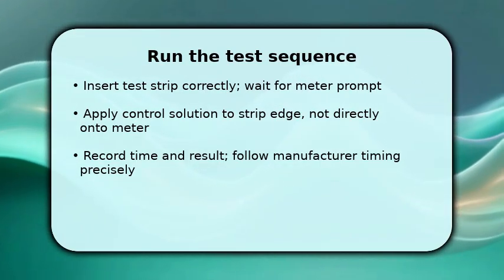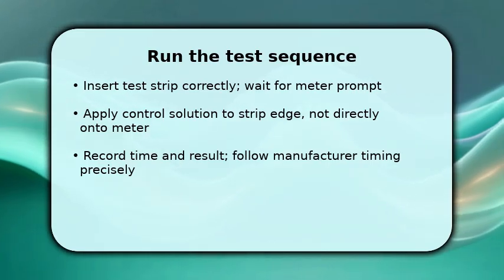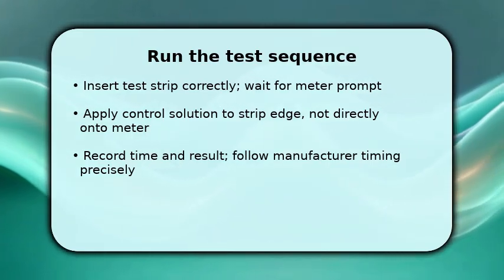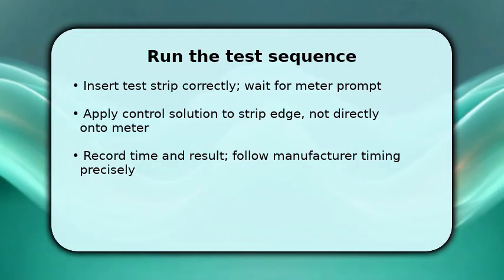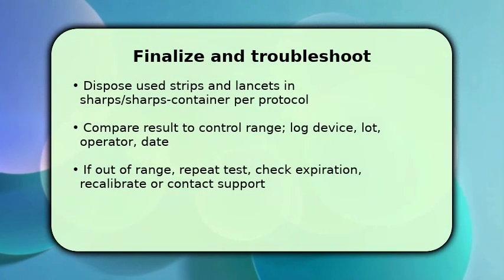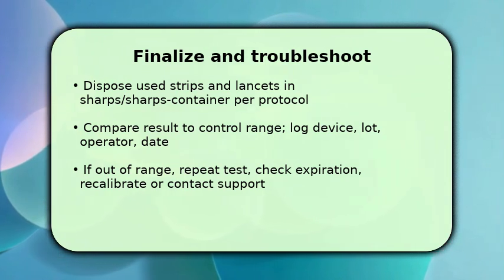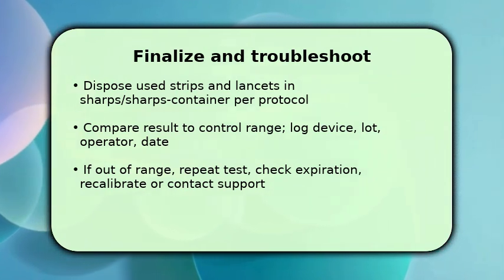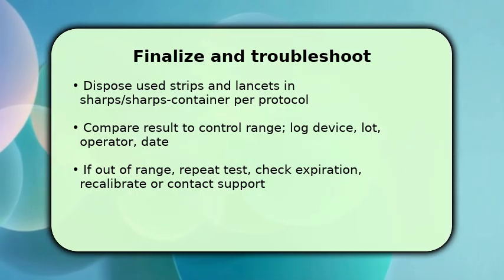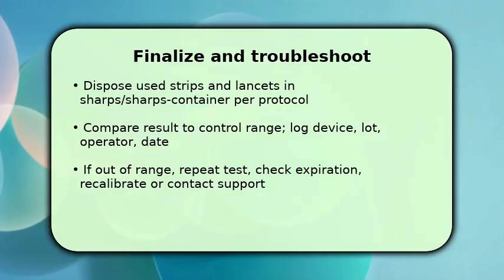If running multiple levels, repeat with fresh strip and solution, and document lot numbers to maintain traceability. You finish by safely disposing of consumables and logging the Quick Check Plus lot, meter ID, and result to maintain QA records. Compare the value to the expected control range. This confirms meter accuracy for patient testing.